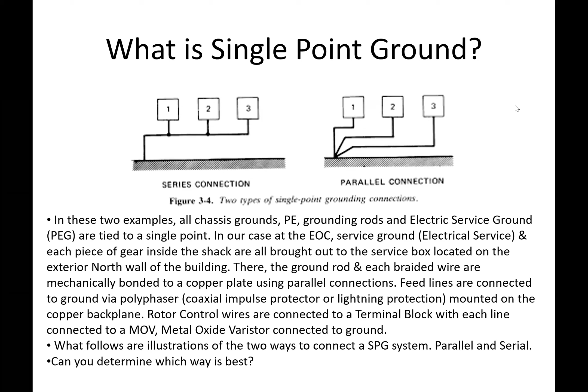The parallel grounding connection, I've got another slide up. Again, this exemplifies the fact that each piece of gear has its own connection to ground, the single point ground. Everything, including the service ground, which comes in from the electrical service, is grounded to that point outside of your building. What's the point of all this?